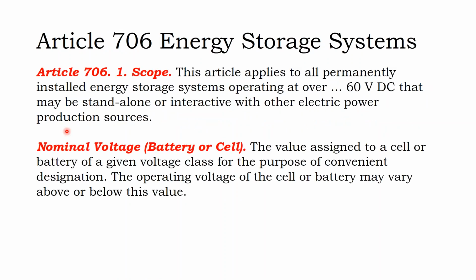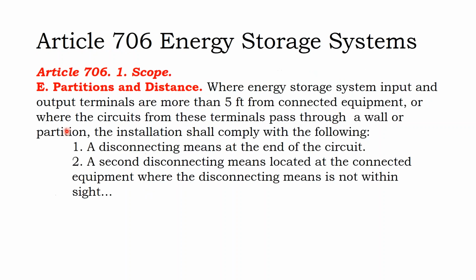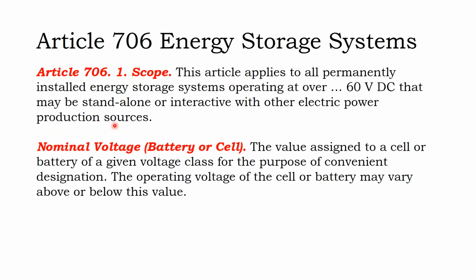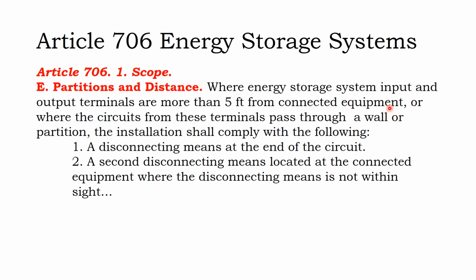As far as batteries go, one thing to keep in mind is batteries are referenced at a nominal voltage. So it's very common to have a 48-volt battery be charged above 48 volts. Maybe a 53-volt or 54-volt state of charge might be charged with a 60-volt charge controller. When your battery bank is more than 5 feet away from the equipment, you'll need not just a disconnect switch at the equipment, but also at the battery bank itself.